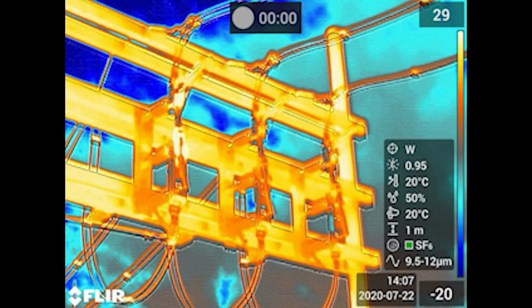This is the same structure but looking through the IR camera of the GF77, and you can see the left-hand cutout is quite hot as compared to the center and the right cutouts. This was a bit of a surprise to us. We weren't anticipating this particular cutout to be hot. It was around 90 degrees centigrade, so this is something that was set for adjustment of the jaws the next time they were out of service. The utility should be a little bit concerned as there was an unbalanced load on the switches at this time.